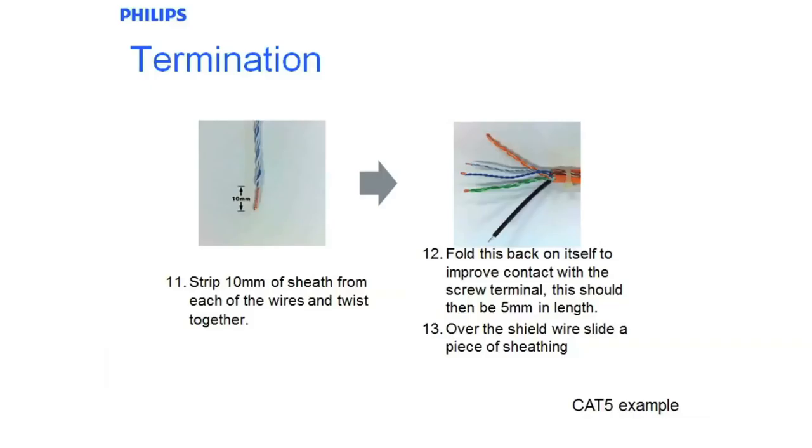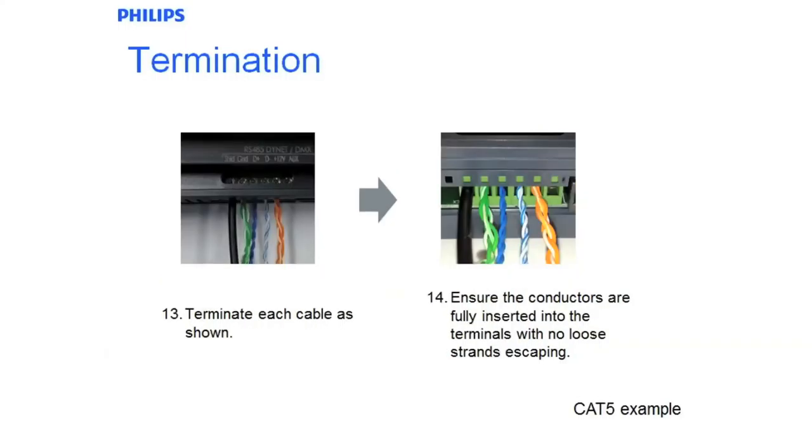Ensure with the shield that you slide some PVC or some heat shrink over it to give it some shielding. If you don't have that available, use some of the outer orange sheath which you have already cut off. Use that and slide that back over as a bit of cheap protection. Terminate each of the cables as shown, making sure there is no excess copper hanging out of the terminals.